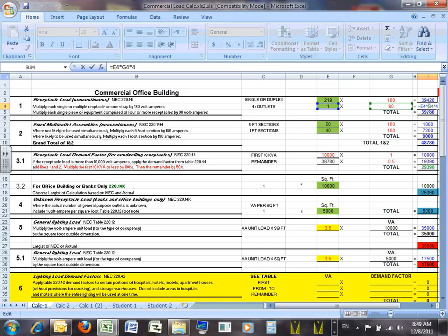Square footage is only for, we're coming to square footage in commercial building, unlike residential. That's a switch that you guys have to do. Square footage of a building, unlike residential, where it covers receptacles as well as light. In commercial building, it only covers light. Cool? That's a very major change between the commercial and the residential.